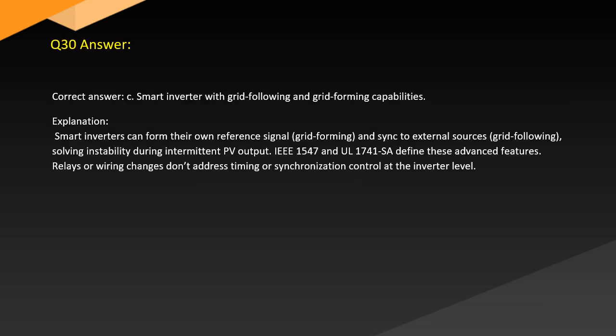Answer. Correct answer: C. Smart inverter with grid-following and grid-forming capabilities. Explanation. Smart inverters can form their own reference signal, grid-forming, and sync to external sources, grid-following, solving instability during intermittent PV output. IEEE 1547 and UL 1741 SA define these advanced features. Relays or wiring changes don't address timing or synchronization control at the inverter level.